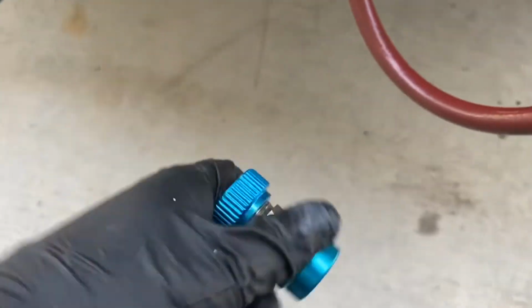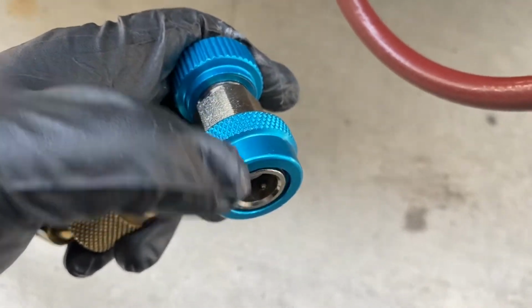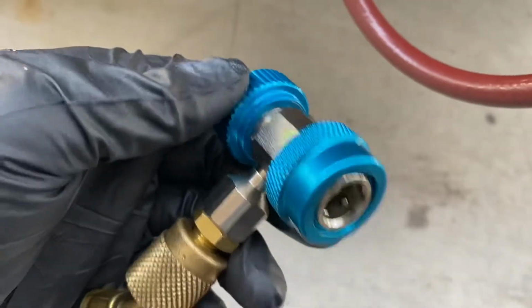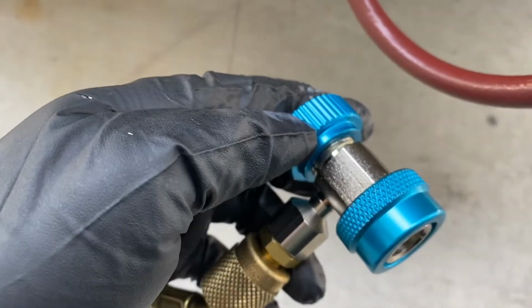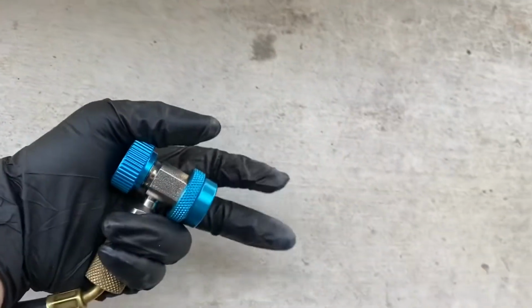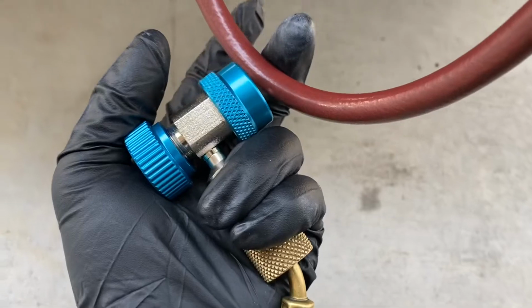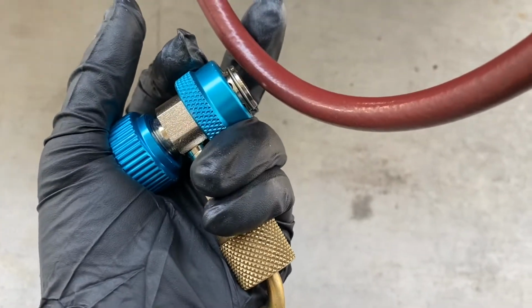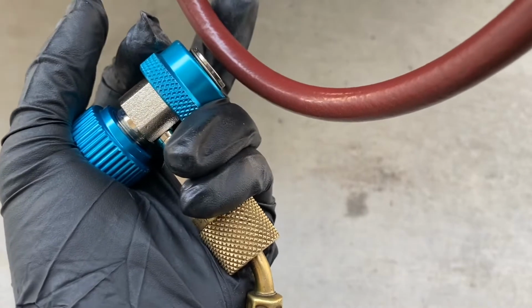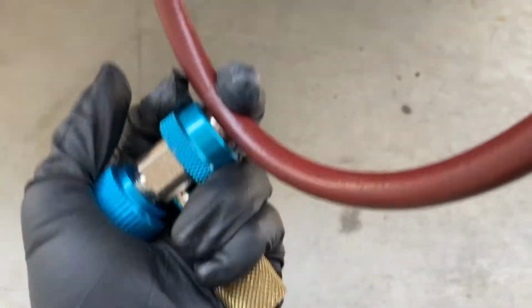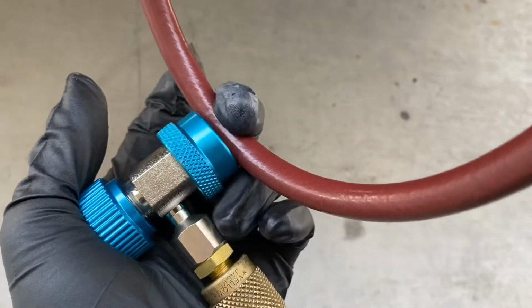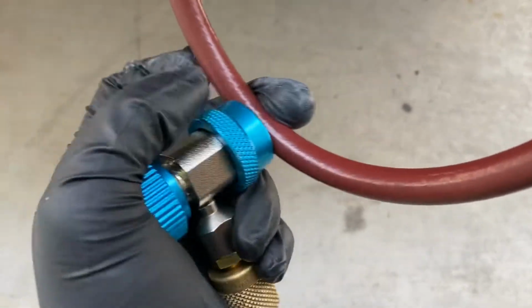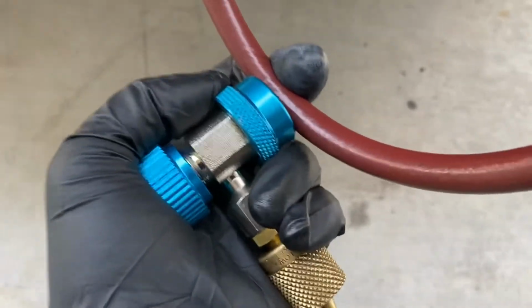Okay, disconnected the quick connector. So how you use it: first you need to open it, this rod should be all the way up, because that rod is pushing on the Schrader valve. As long as you bring this rod back to the maximum top, you hold your pipe, apply pressure on the spring, push it to the maximum using my finger, the middle finger, then release the spring, and you can wiggle it and it should sit well.